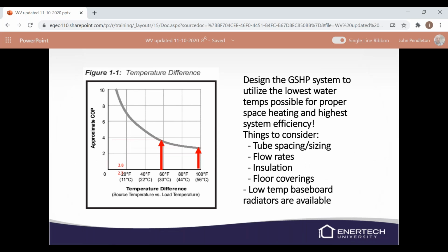Here's a little chart of the COP of a unit. Basically, you can see how it'll raise. We're showing the temperature difference between the source temperature and your load temperature. So as those get farther apart, the COP of the unit gets lower. So if we can have a 20-degree temperature difference, we're going to be running a pretty good COP of like 7.5. As it gets farther apart, we're going to drop down. So you also have to take into consideration tube spacing and sizing, your insulation, your floor covering, and the types of baseboards that you're using as well for those temperature set points.